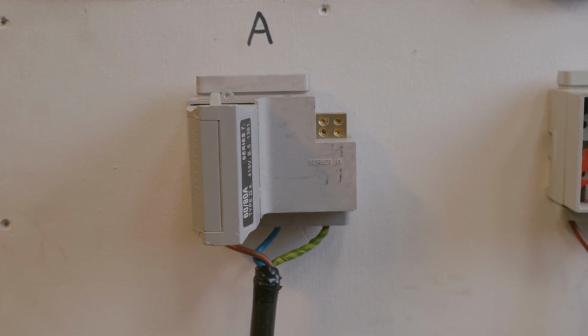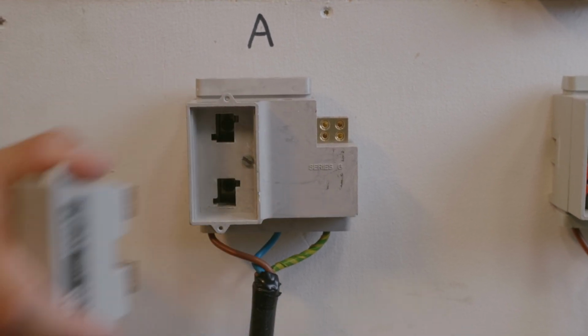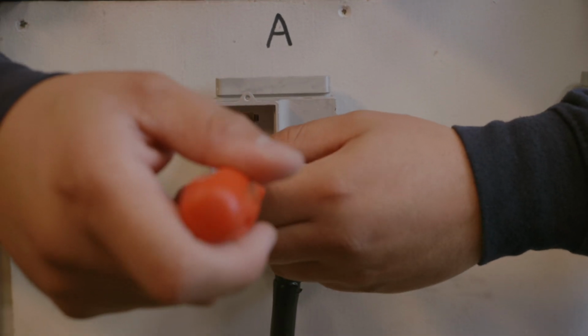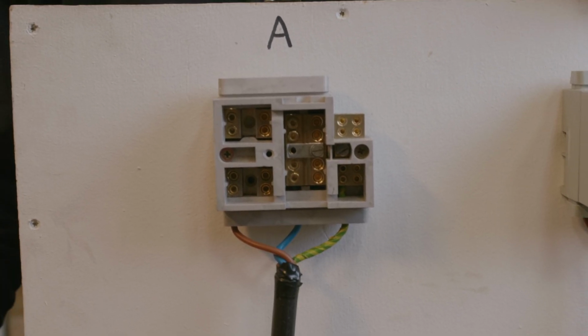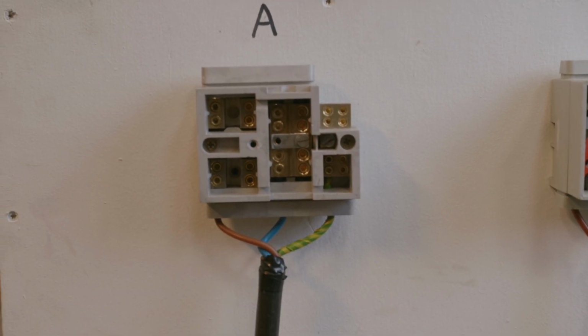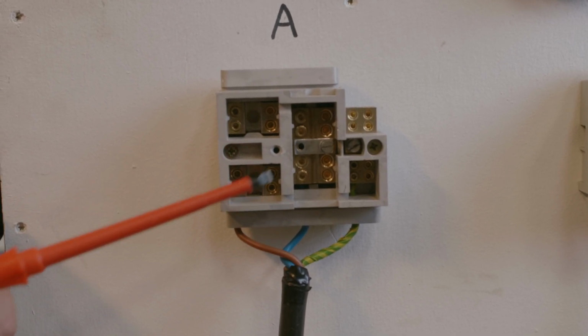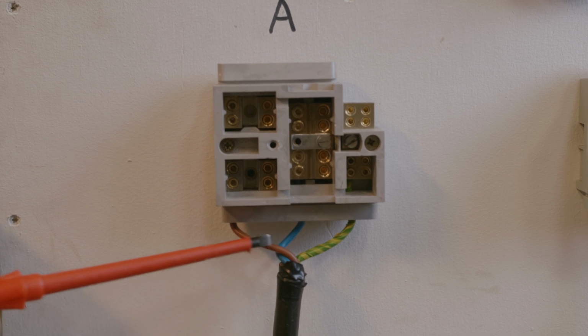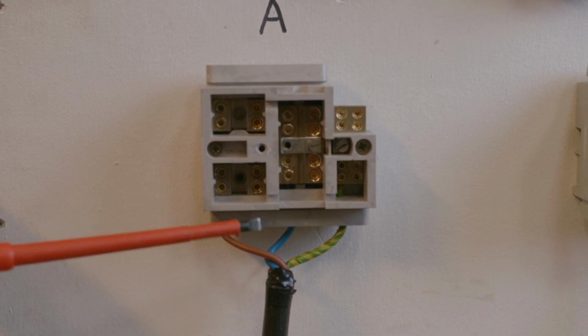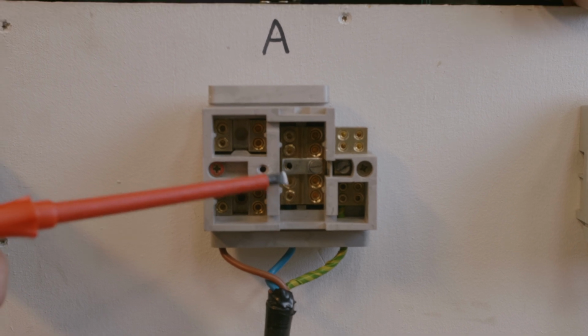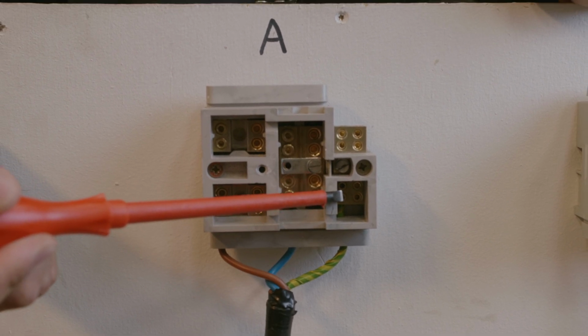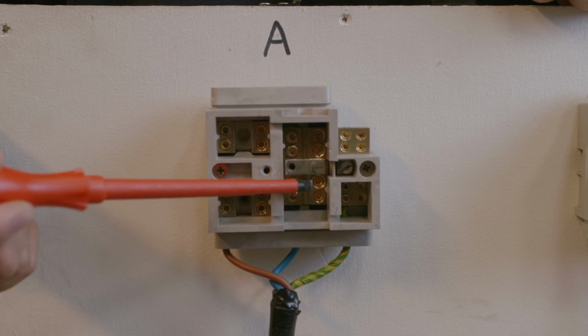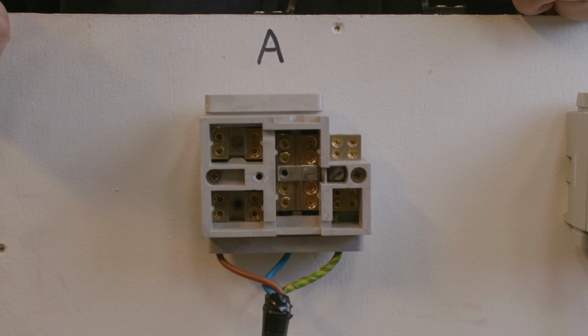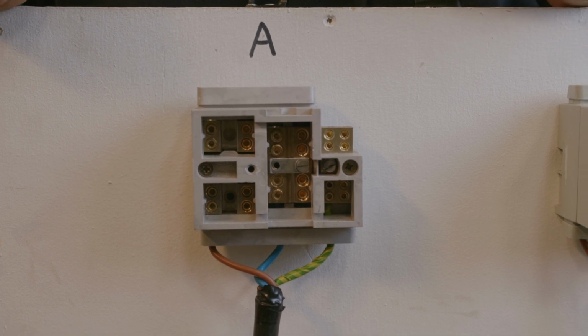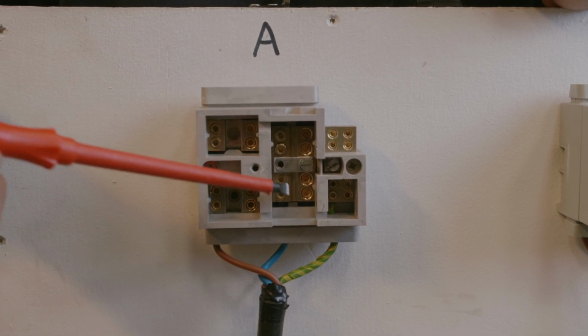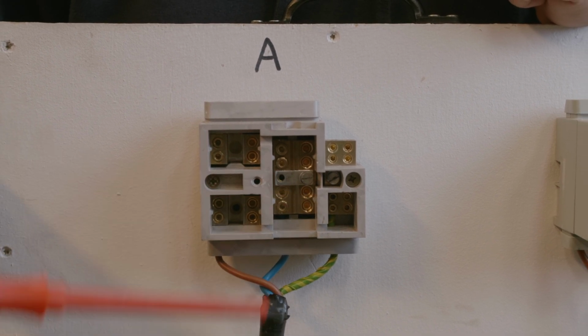So if we remove that fuse, remember you must get DNO authorization to be able to remove the main fuse and then check inside. Once that has been removed and you take off the cover there, you can quite clearly see the difference within that cutout. You have the point at which the line conductor comes in, a separate point there at which the neutral conductor comes in, and another separate point there where the earth comes in as well. As you notice, both the neutral and earth are completely separate. So that's how we would identify that this is a TNS system, because both the neutral and the earth are completely separate all the way back.